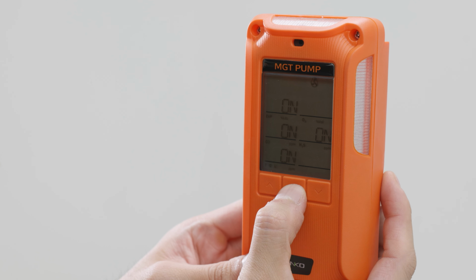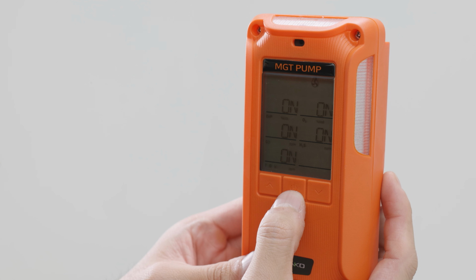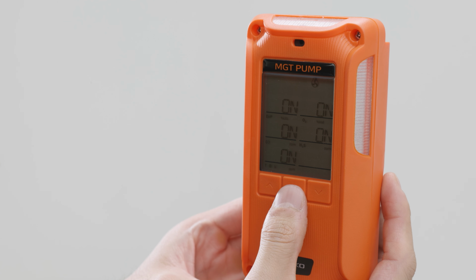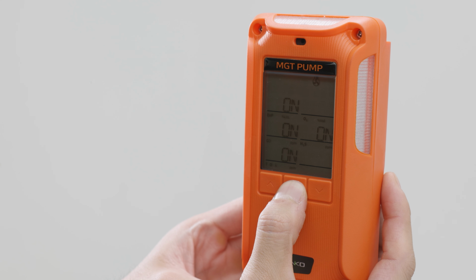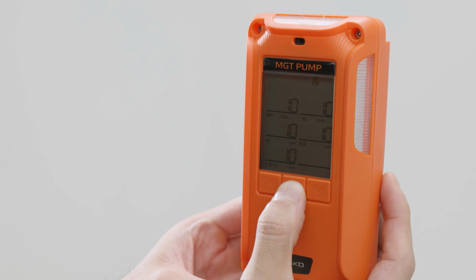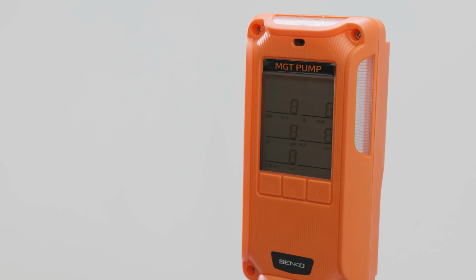After selecting Zero Run, a sensor on-off selection screen appears. You can select the target gas and enable or disable calibration as needed, allowing calibration to be performed only for the selected sensors. After selecting the sensors to be calibrated, press and hold the Select button for approximately 3 seconds to start the 10-second zero calibration countdown automatically.